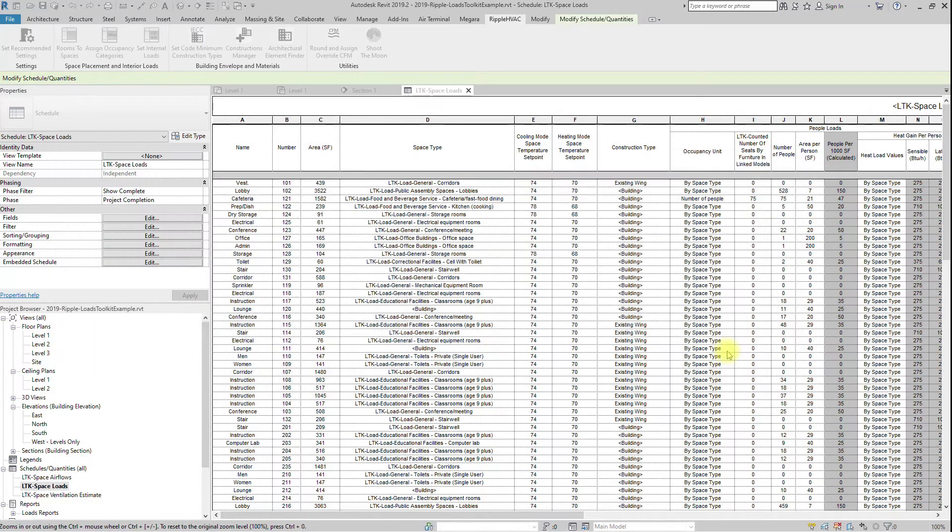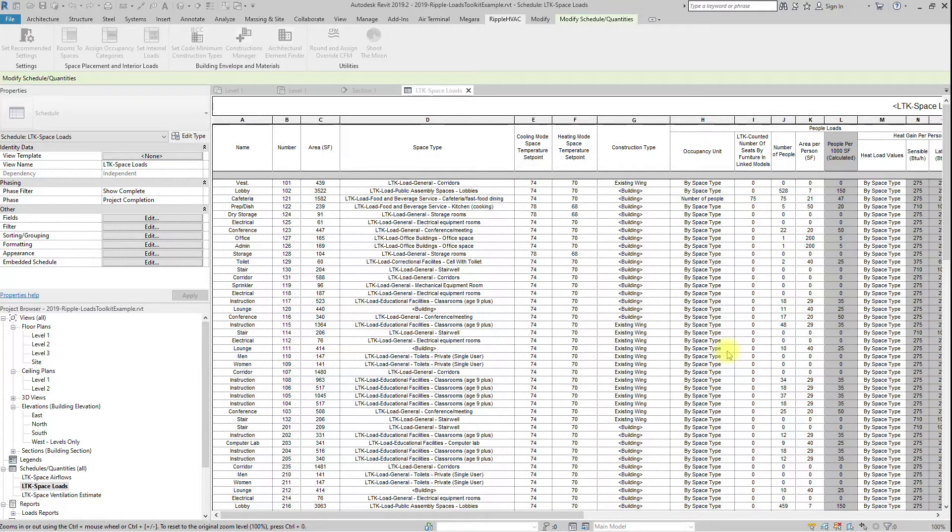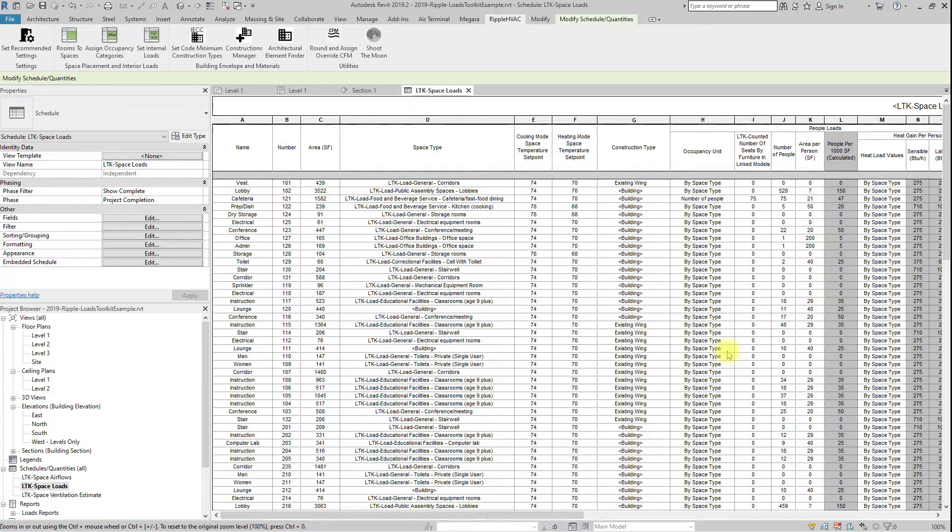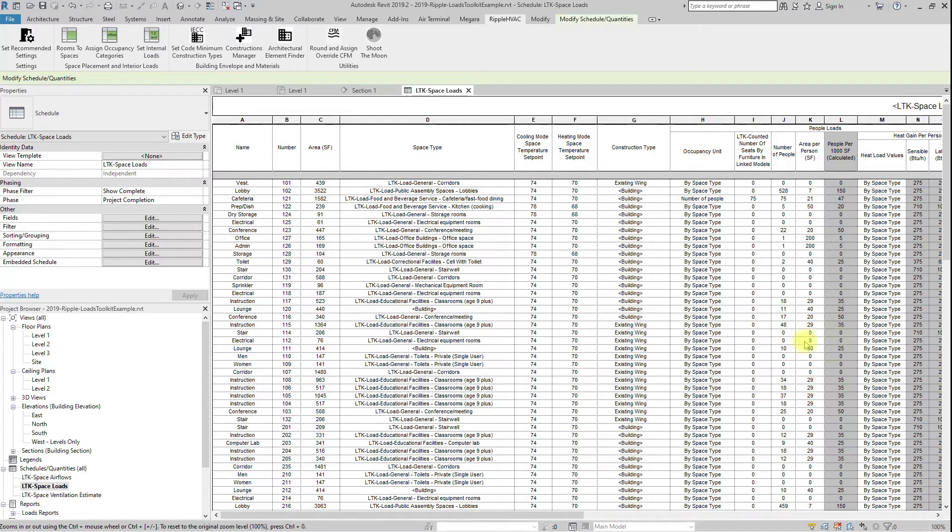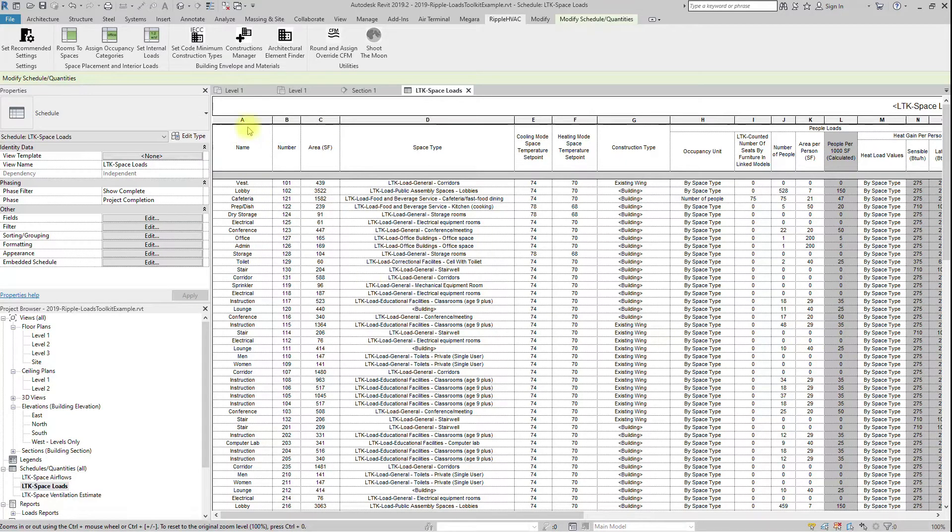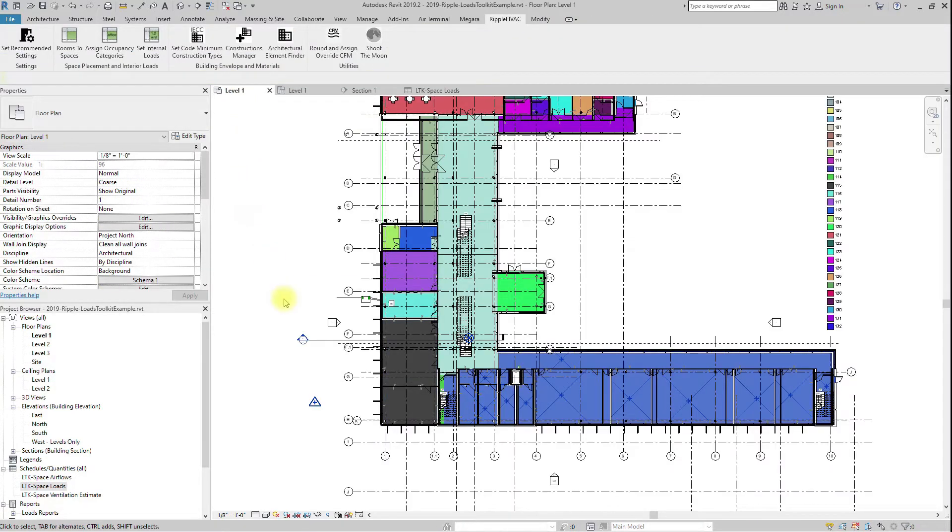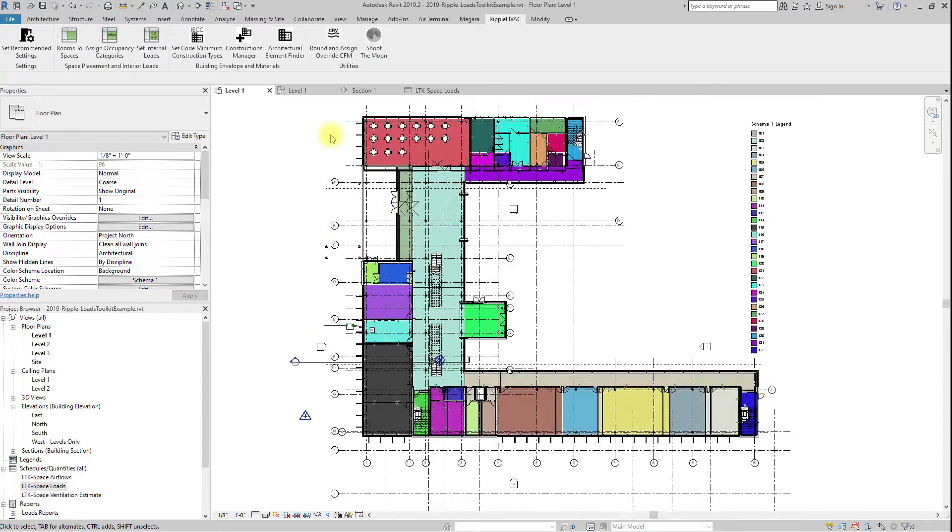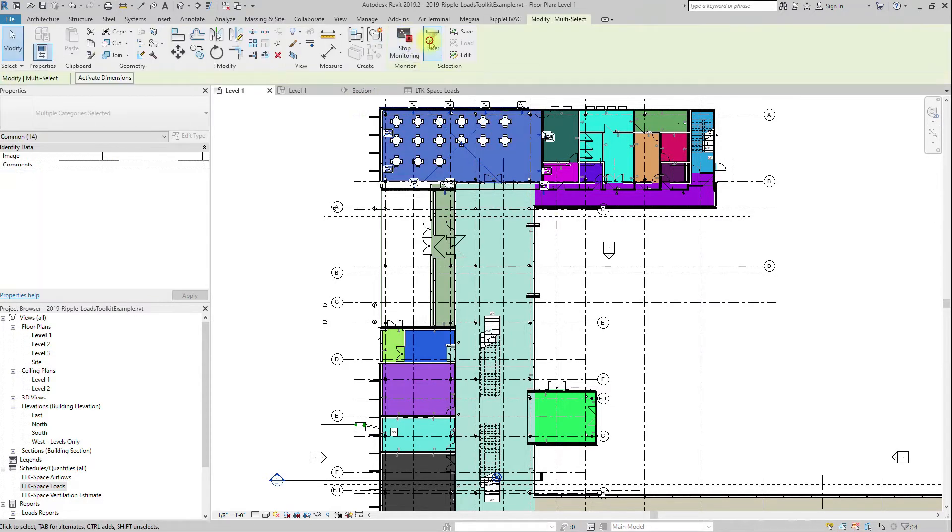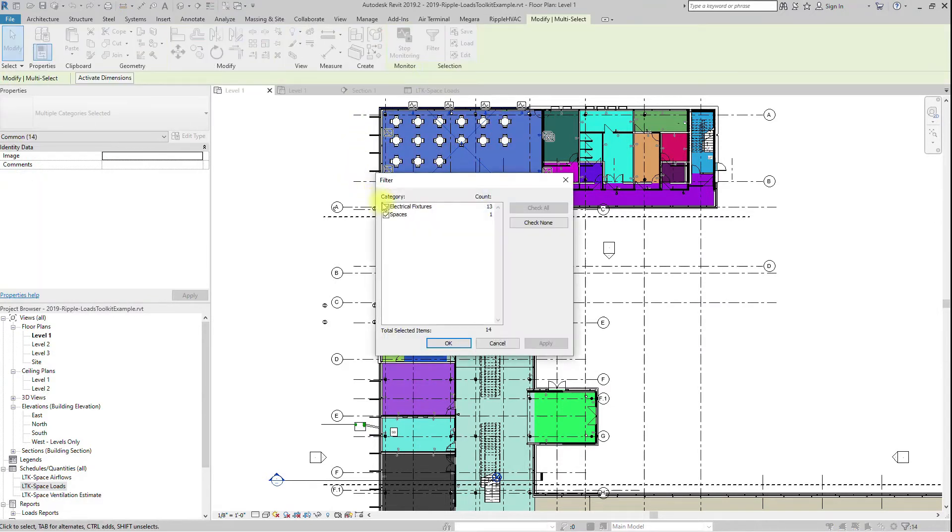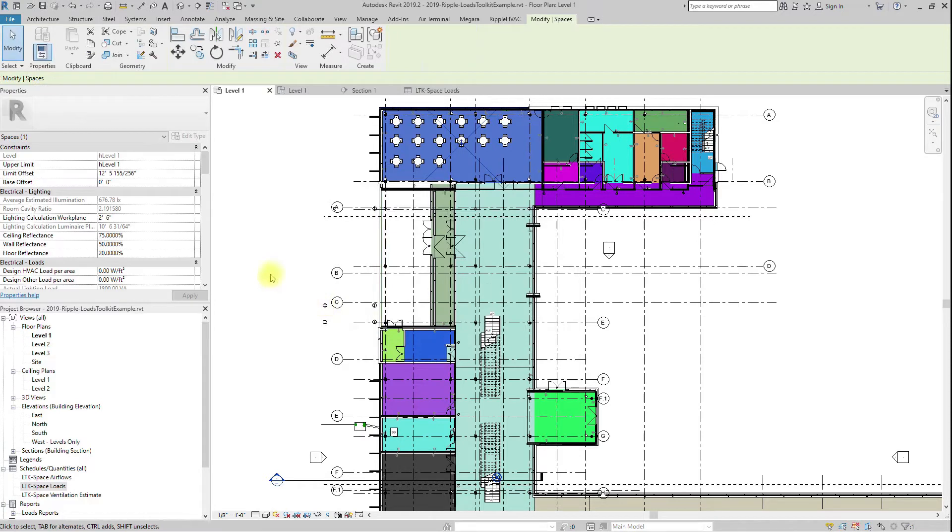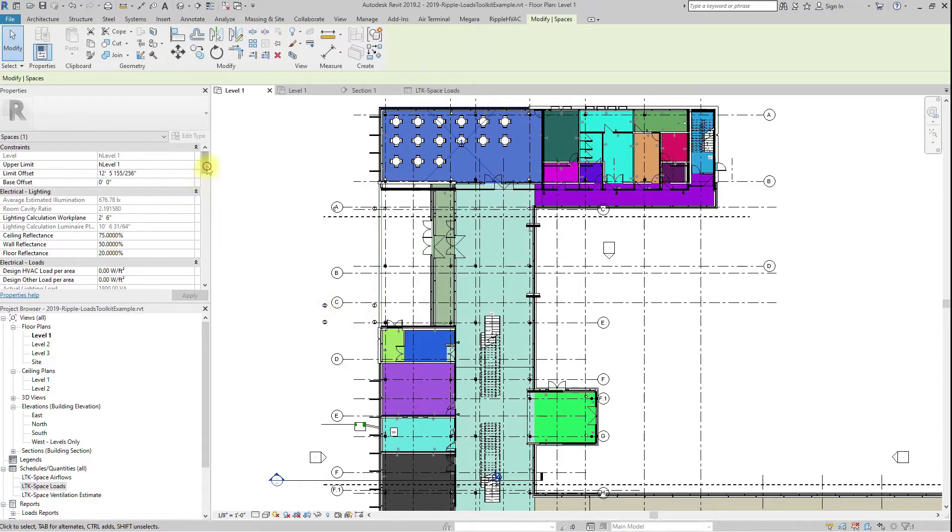When overriding architectural elements, you can only select one set of thermal properties for each category. This selection overrides every element of that category in the space. This only becomes a problem when a single space has two different construction types. If the thermal properties are close enough, it may be practical to pick the worst thermal properties and apply those to the whole space. This will give you slightly conservative load calculations but will save you a lot of time.